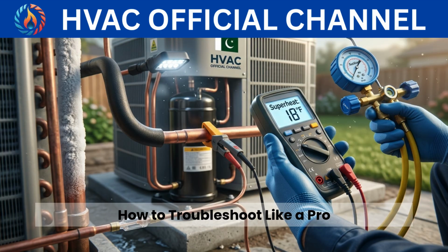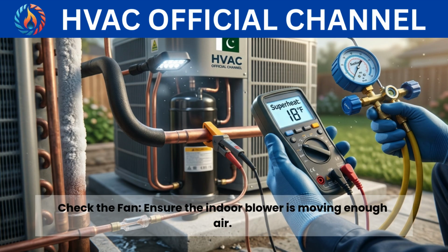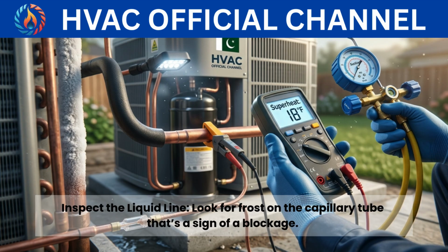How to troubleshoot like a pro. Follow this checklist every time. Clean everything first. Never check gas levels on a dirty AC. Clean the filters and coils. Check the fan. Ensure the indoor blower is moving enough air. Check superheat. If suction pressure is low and superheat is high, it's a leak. If superheat is low or normal, it's an airflow issue. Inspect the liquid line. Look for frost on the capillary tube. That's a sign of a blockage.